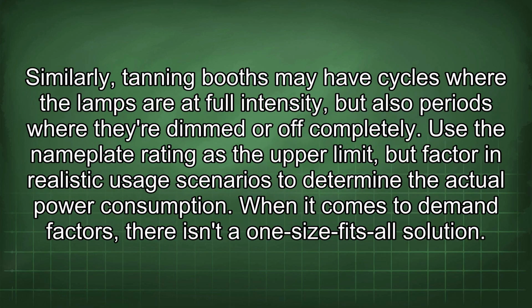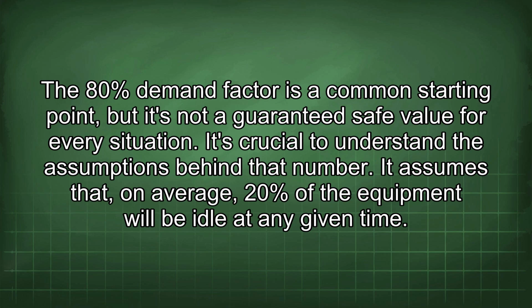Similarly, tanning booths may have cycles where the lamps are at full intensity, but also periods where they're dimmed or off completely. Use the nameplate rating as the upper limit, but factor in realistic usage scenarios to determine the actual power consumption. When it comes to demand factors, there isn't a one-size-fits-all solution. The 80% demand factor is a common starting point, but it's not a guaranteed safe value for every situation.